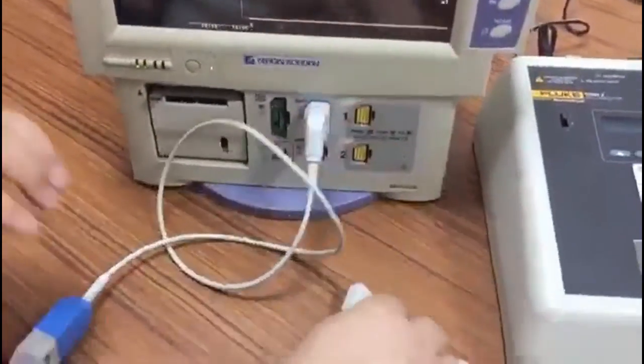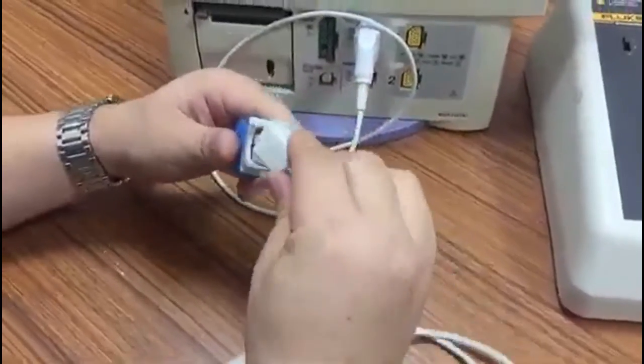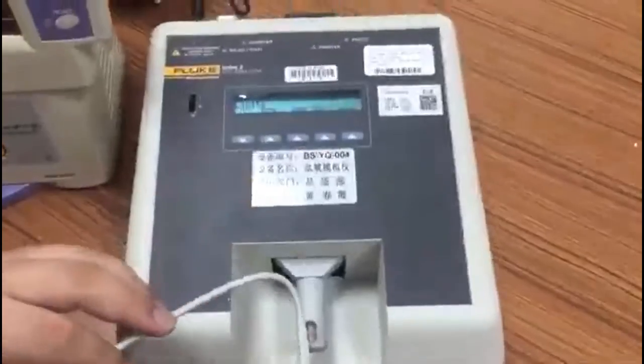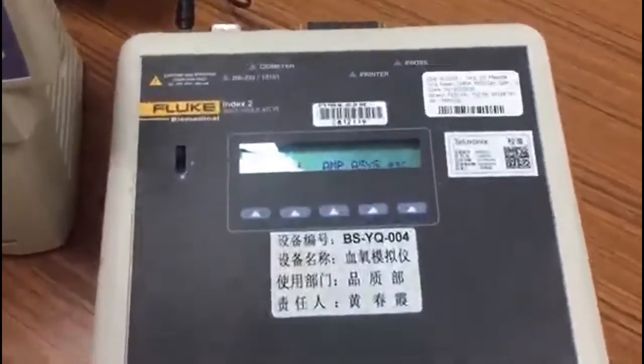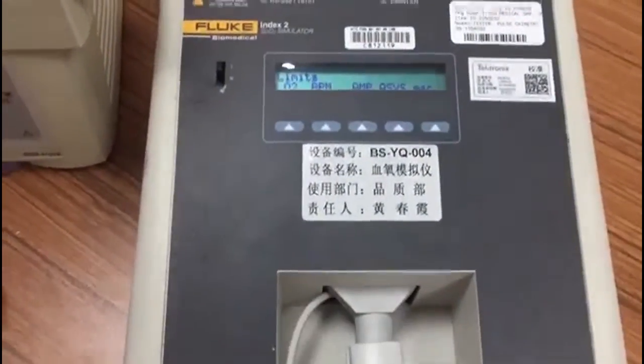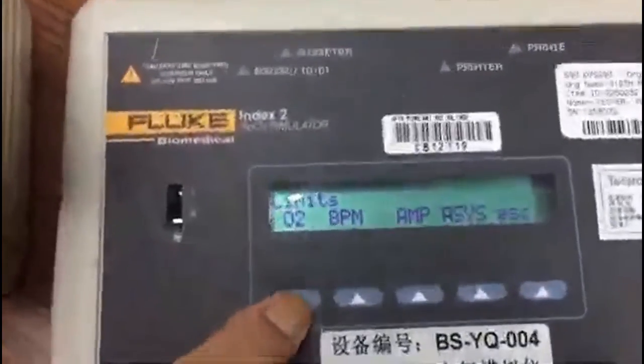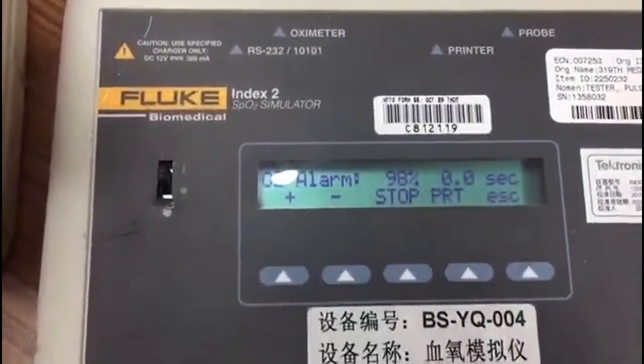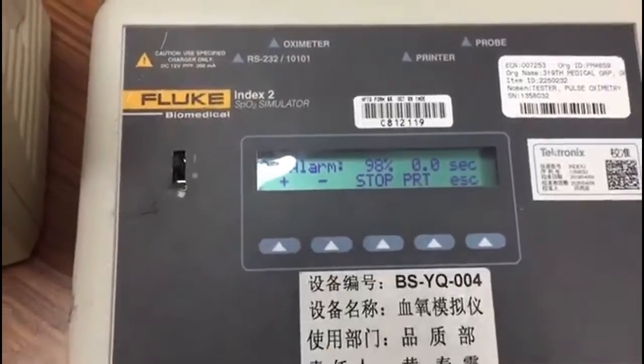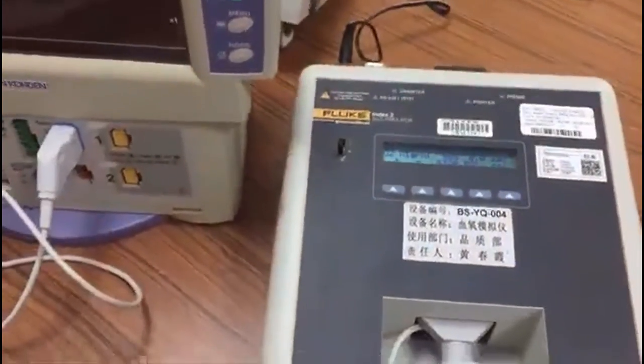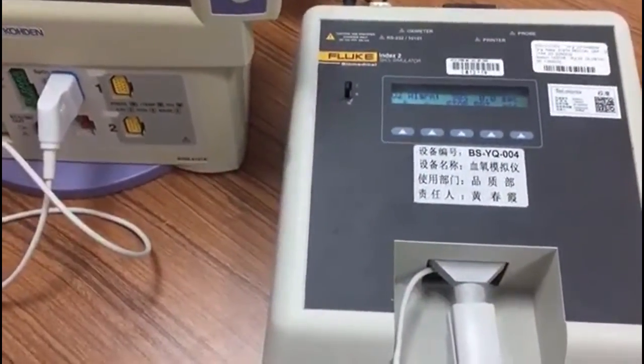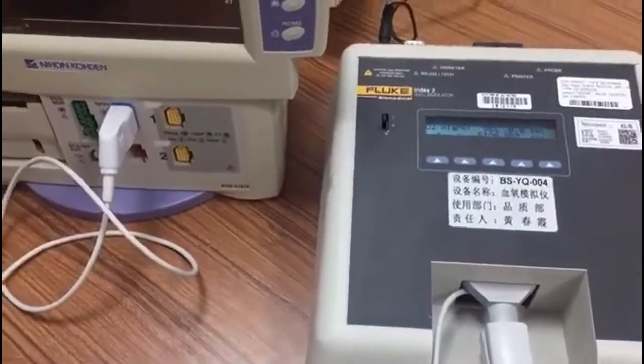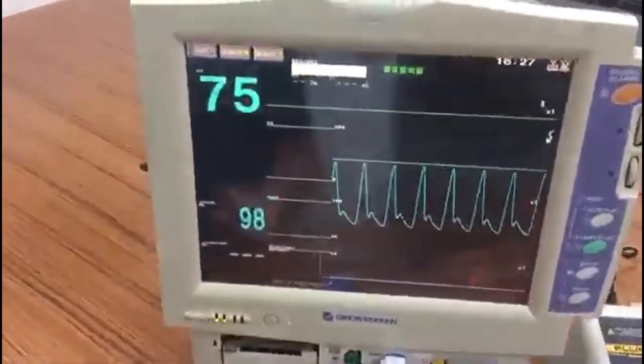We connect the cable with the machine. SPO2 connect with the extension cable. This is the SPO2 simulator to check the accuracy of it. Set the oxygen saturation to 98, and we need to check the machine to see whether it is at 98. Yes, great. So this cable is accurate.